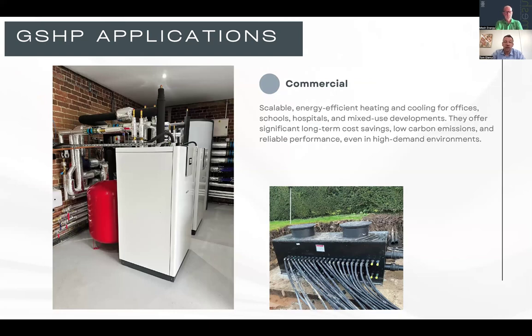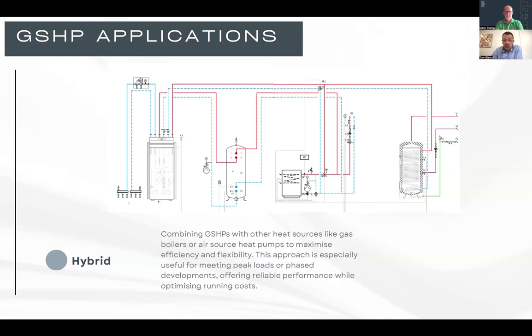Here you can see different installations where you've got a larger residential property. This property, for example, had 33 boreholes, and you can see larger manifolds, which you can almost walk into as a chamber, and you can adjust the flow into each probe. And yeah, so larger units, three-phase units, suitable for large older properties, schools, hospitals, other commercial properties. And here you can see what I mentioned earlier. It's a bivalent or hybrid system where you've got the boiler in between those two cylinders, which can provide backup, or also provide heating and hot water instead of the heat pump in case the temperature outside drops too low or the property has too high heat losses for the system.